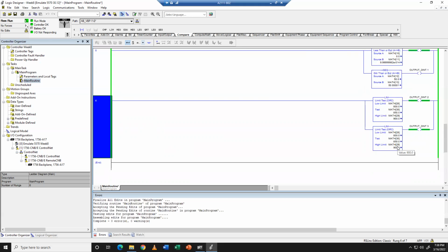If you need something to happen between values, you can set this up as an accumulator. You can have these as accumulators to count parts, have things happen with so many parts cycled through a system. I've even seen some HMI systems like touch screens for assembly lines have people log in, entering a code, and they'll use a limit inside the logic so that if somebody's code falls between a certain range, they're an administrator, and it allows them to change set points.